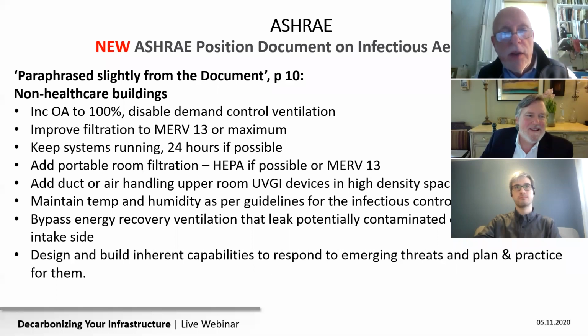Here at ASHRAE's fundamentals, they have a white paper, it's a draft, but it recommends increasing outside air to 100%, disabling demand control ventilation. So basically, take your energy conservation, open the window, throw it out. Improve filtration. Does it take a little more fan horsepower? Yes, but probably not much in the scheme of things. Keep systems running 24 hours a day, instead of scheduling and preheating for an hour or two, just run it all day. Put more air and more filtration in the room. And bypass energy recovery ventilation.